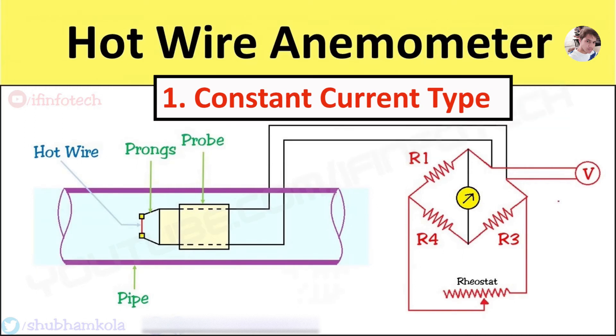First is constant current type. In this type, variation of flow results in change to wire temperature. Resistance of wire also changes. This change in resistance then becomes a measure of flow.